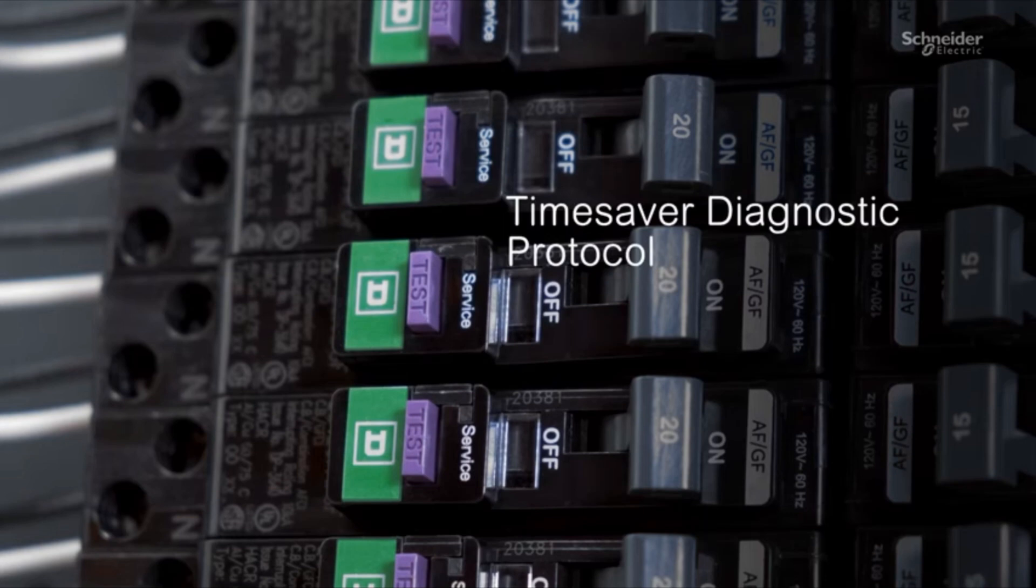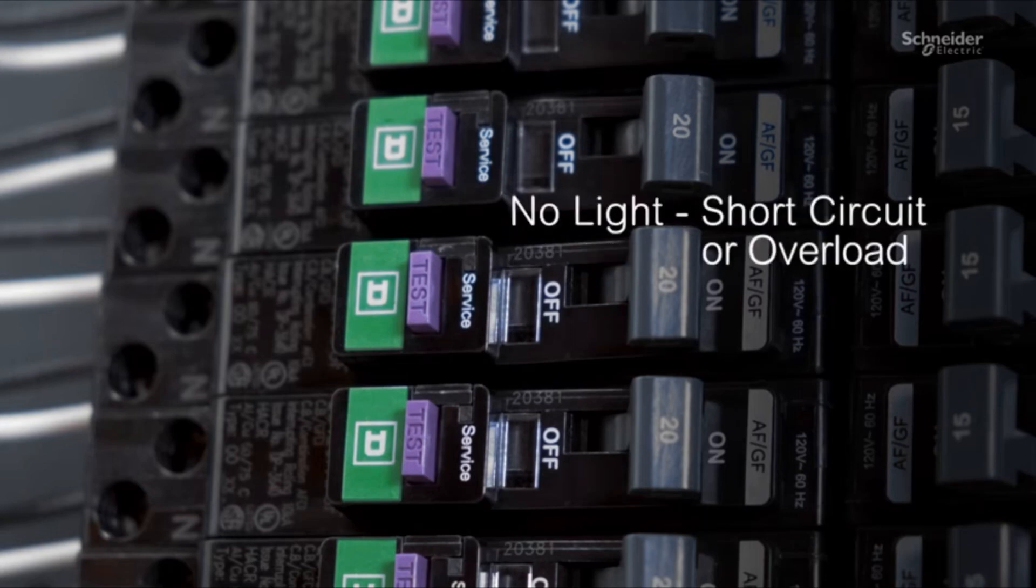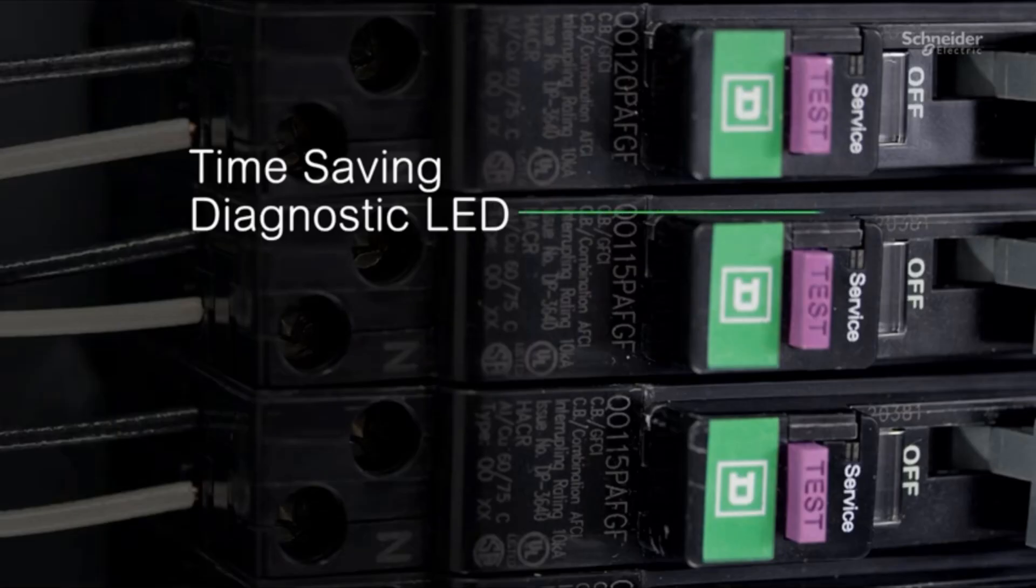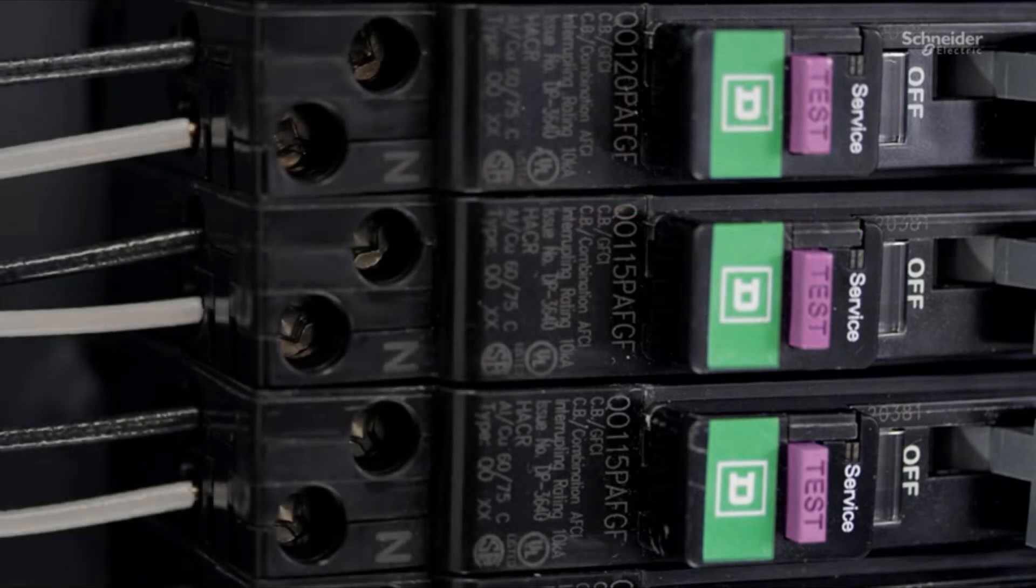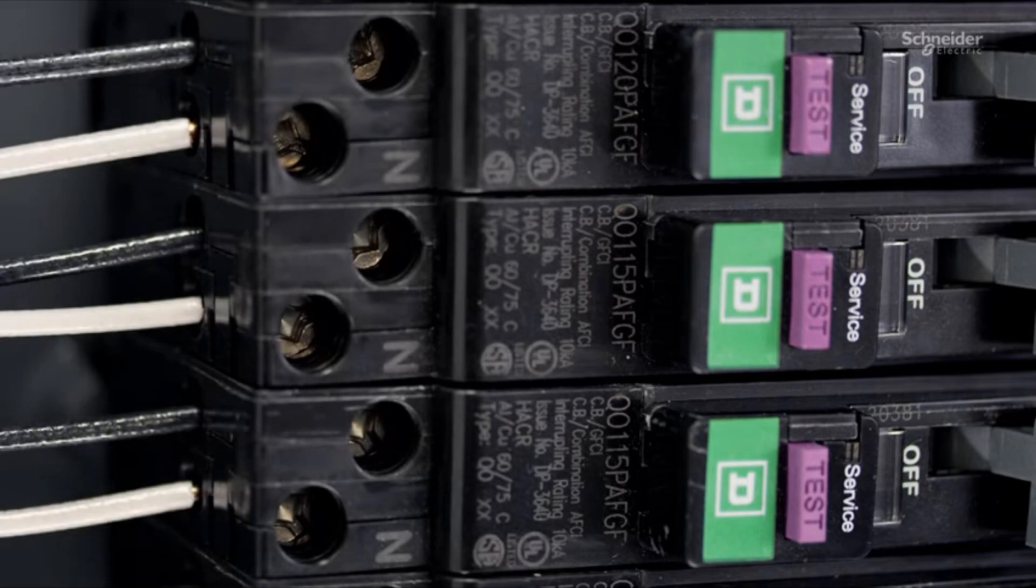If the LED does not turn on, there's been a short circuit or an overload condition, and a service call can likely be avoided. The time-saving diagnostics LED provides a visual indicator for quick and easy electronic fault diagnosis, saving contractors time and money.